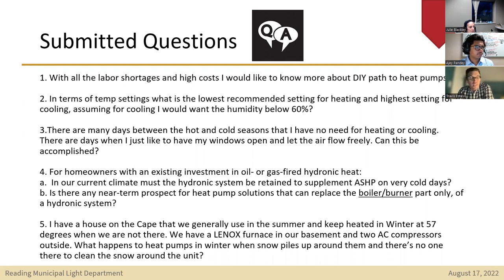Sizing matters. If you oversize a heat pump, it's consequential for a couple of reasons. One is that it can result in the system not operating as efficiently as it should—you'll find it's turning on and off a lot, referred to as short cycling. Short cycling results in a larger electricity draw during that time frame versus a system sized smaller that runs at a lower speed more continuously. When we've put monitors on systems, we've seen these spikes occur, and those oversized systems lead to higher bills and decreased comfort. On the air conditioning side, you actually lose some of the dehumidification benefits provided by heat pumps during summer because of being oversized and not reaching that run rate state. So definitely make sure these are sized correctly.